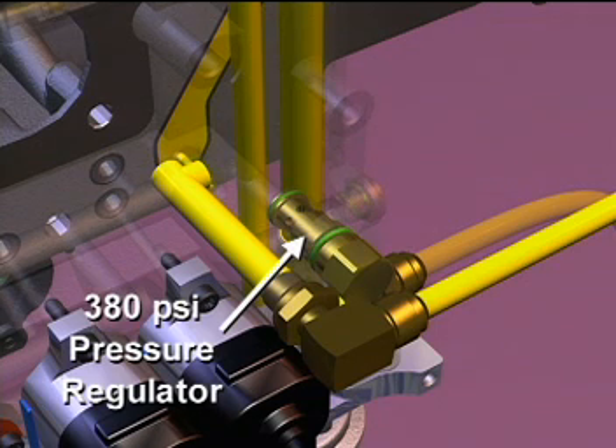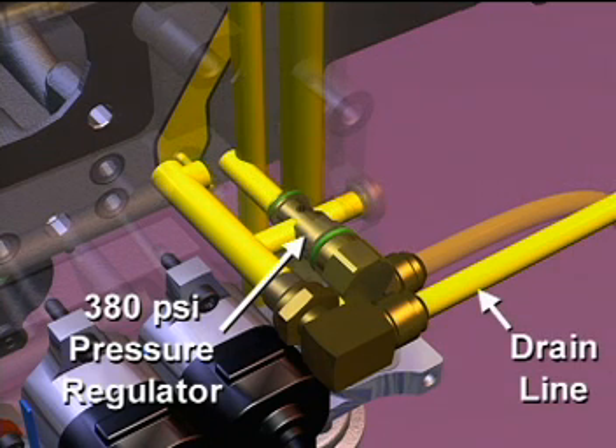The 380 psi high-pressure regulator installed in the IFSM between the gear pump and the filter is a safety valve to prevent damage in case of a stuck fuel shutoff valve or other blockage in the fuel lines after the gear pump. Any fuel flowing through the high-pressure regulator is dumped back to the drain line in the IFSM and then returned to the fuel tank.